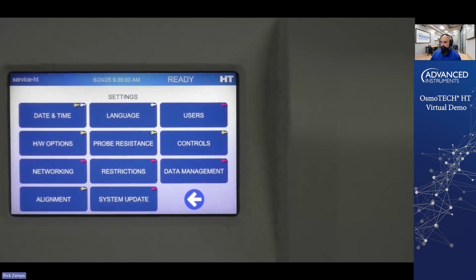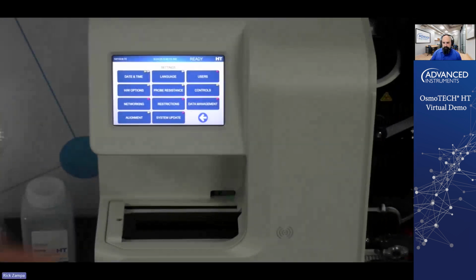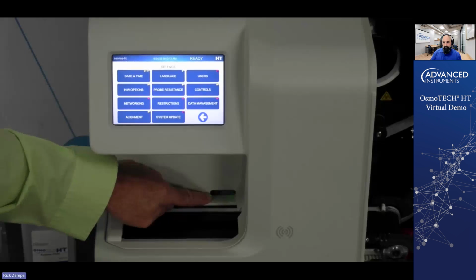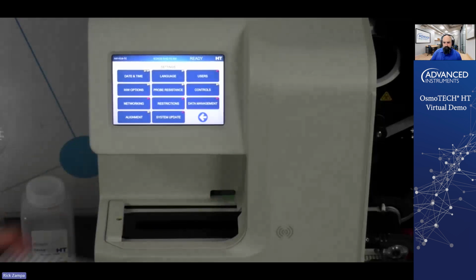There is not a barcode reader that can be used to read a user ID. You could set up a secondary barcode scanner, but the only barcode reader right now is here on this part of the instrument, where it's reading the barcode on the plate. However, for sample IDs, if you were using a secondary barcode, it could be a 1D or 2D barcode.